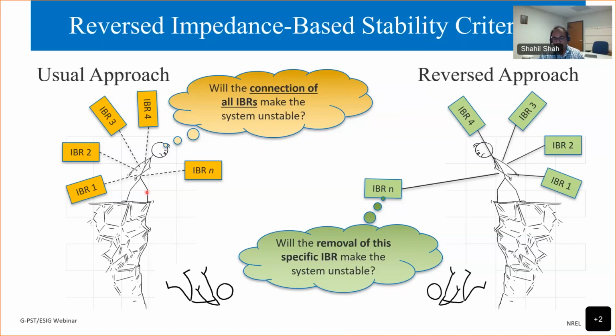So we start with a stable system and try to answer questions on how each IBR is playing a role when we see these underdamped oscillations. In this reversed approach, the fundamental premise is that the integrated system is stable, with all the IBRs. Then I select a specific IBR and try to answer the question of what will happen if I remove this IBR, whether it will make the system unstable. In this case, I need to do the impedance scan of only that IBR and the impedance scan of the network looking from that IBR, so only from one port. And we can repeat this process as many times as you like to understand how each IBR is impacting the stability of the network.